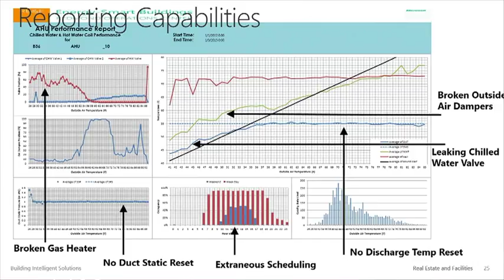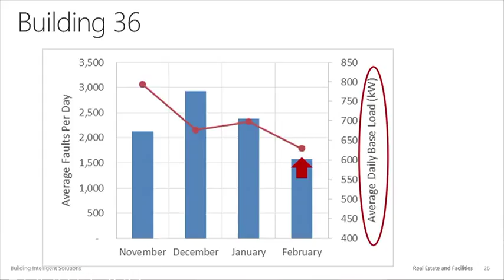So we started connecting this building in November, and we started addressing all the faults about January. So we went from 3,000 faults down to 1,500. What we saw is the energy consumption went down by 20%. This is one of our LEED buildings that I would never have guessed this of. One of our other buildings, City Center, this is the largest building in our portfolio. And this is one of the Bing buildings. And we found 17% energy savings in 5 days. And there were 3 main drivers. One, this building is fed by one air handler at 600,000 CFM, and the economizer was stuck closed. The building management system says, hey, it's working great, life is good.